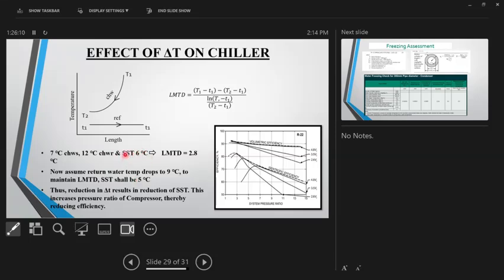Earlier it used to suck the gas from 6 degrees centigrade to condensing temperature. Now it needs to slightly go down, pick the gas at 5 degrees centigrade and push it up. So the reduction in delta T is a reduction in SST. This increases the pressure ratio, and that's how the chiller efficiency gets affected. Is this clear? The intent is not really to explain the full low delta T syndrome, but it's just an introduction. So two critical parameters: over pumping, so wastage in pumping energy, as well as chiller energy. So low delta T syndrome is a problem always.